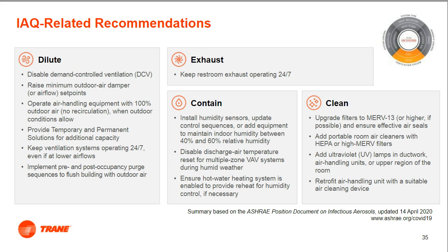Exhausting a space is critical to making sure that the contaminated air is removed from the occupied building. One critical space that should always have some sort of exhaust method during occupied times are bathrooms. It's also recommended that exhaust systems should also be operating during times of pre- and post-occupancy purges, like during the dilution stages.